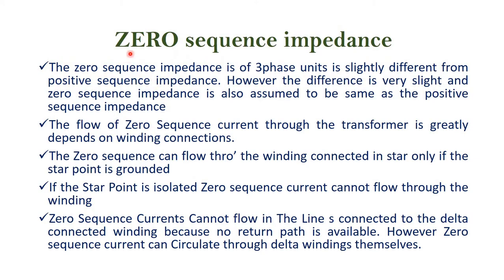Next I am going to explain the zero sequence impedance of the transformer. The zero sequence impedance of a three-phase unit is slightly different from positive sequence impedance. However, the difference is very slight and zero sequence impedance is also assumed to be the same as the positive sequence impedance. The flow of zero sequence current through the transformer greatly depends on winding connections.